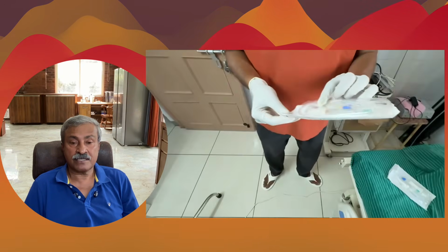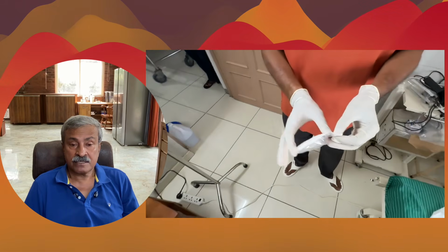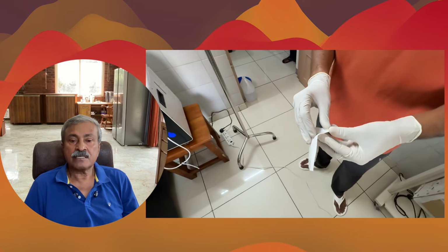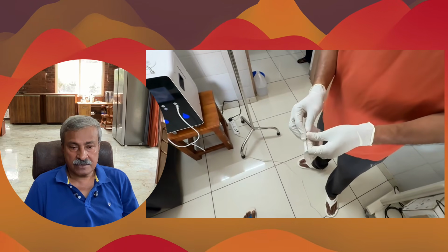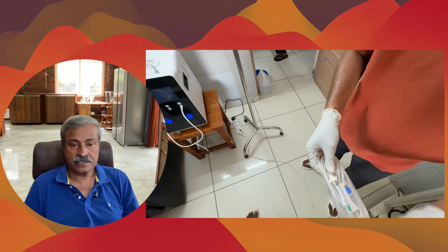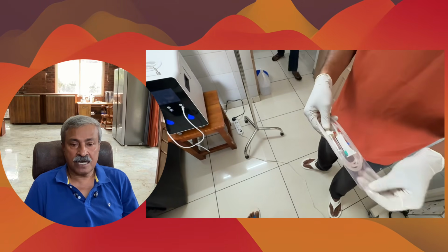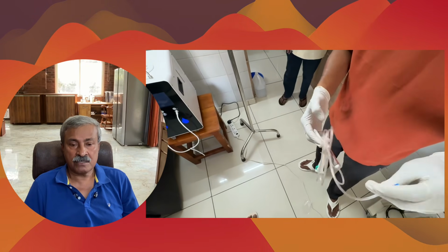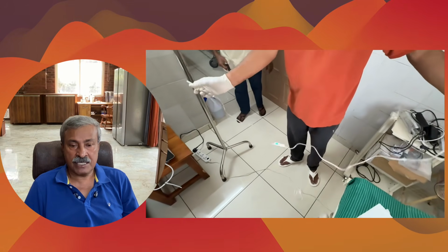As we are injecting close to 600 ml per minute in a 100 ml bottle, it is essential to have a large air vent to allow the excess hydrogen after saturating the bottle to escape through an air vent.